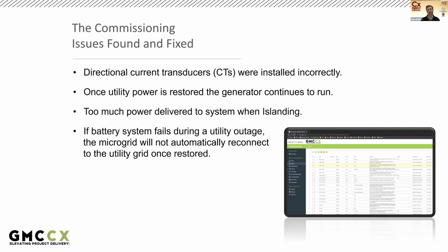Finally, if the battery system fails during a utility outage, the microgrid will not automatically reconnect to the utility grid once it's restored. So if there is a battery failure, CB1 stays open. There's no way to automatically transfer emergency loads back onto restored utility power. This also must be done manually.